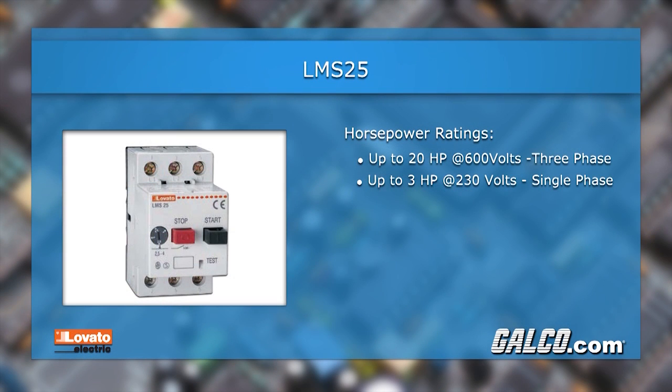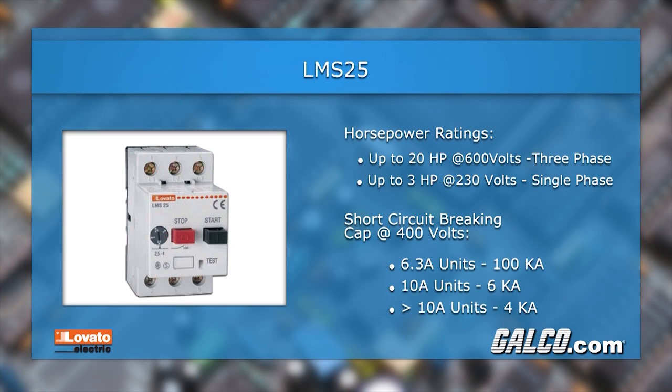Units are available with horsepower ratings up to 20 horsepower at 600 volts for 3-phase and up to 3 horsepower at 230 volts for single phase. The short circuit breaking capacity for units at 400 volts is 100 kA for units rated up to 6.3 amps.